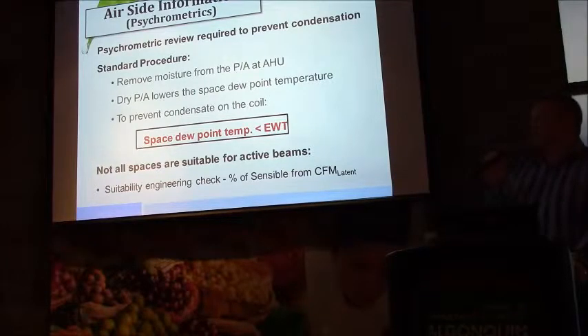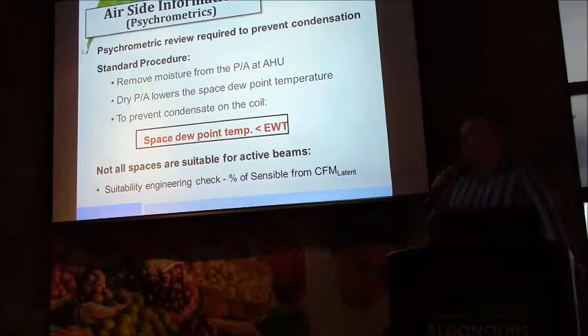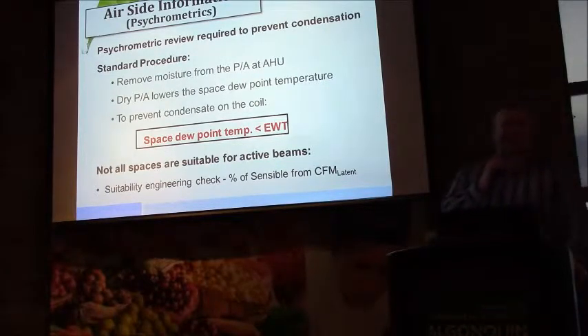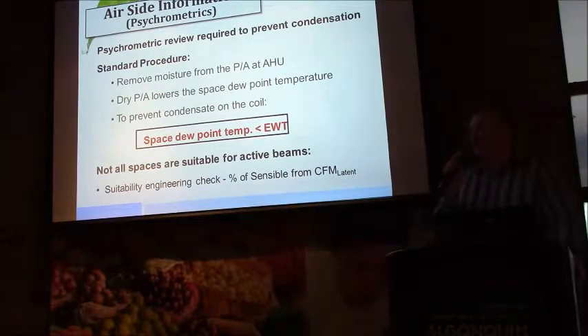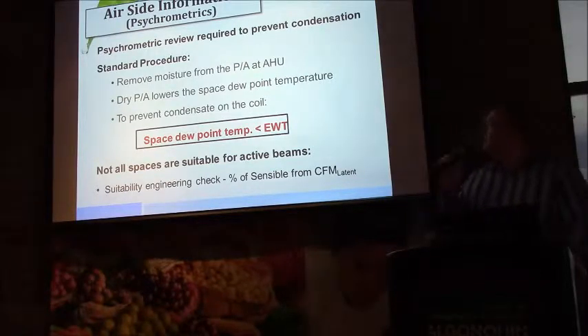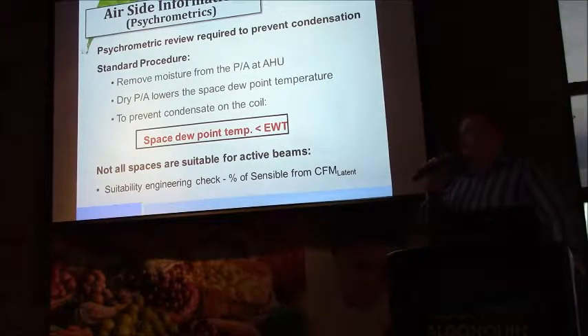So again, the goal of our three selection criteria on our primary air is to remove the moisture from the primary air at the air handling unit. But that's our only means of dehumidifying the space. And if we do anything wrong in designing active beam systems, that's our opportunity for mischief. We must check the psychrometrics in each of these spaces and ensure that our design criteria are met. There are reasons why we would allow the primary air to be driven lower, obviously to get closer to the minimum ventilation volume that we would need to supply to the space, but there's an energy cost to that, and the equipment can also become expensive to really dry out the primary air. But the cardinal rule of beam design, obviously, is that the space dew point must be below the entering water temperature to prevent condensation on the coil.